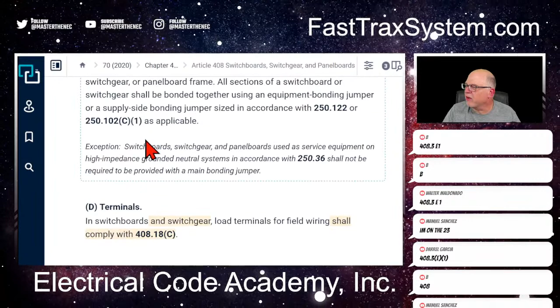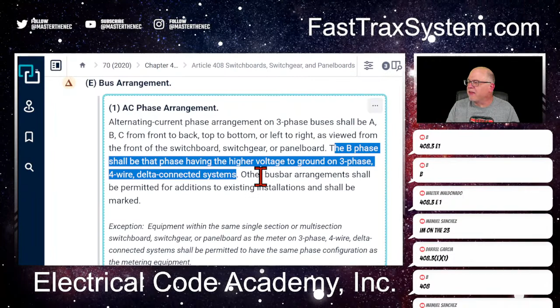All right, so then we're going to go down and see what we're looking for. Bus arrangement, E. Okay, and then we see the B. We see a mention of B—remember, triggers, questions about B. And it says the B phase shall be the phase having the higher voltage to ground on 3-phase, 4-wire delta systems. So the answer is most certainly B, and this is E1 in the 2020 edition of the National Electrical Code. So we'll go back.